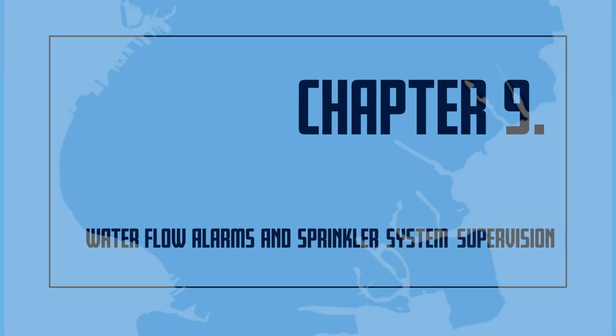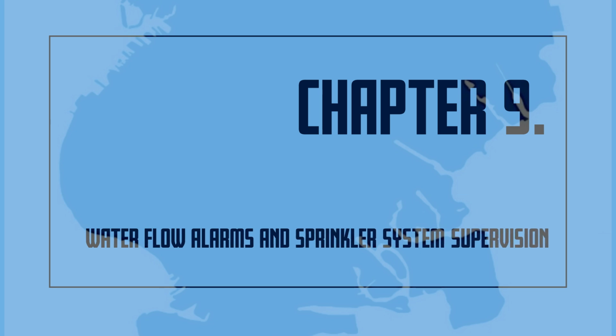9. Water flow alarms and sprinkler system supervision. Sprinkler systems should have devices and equipment for signaling when water flows through risers or mains supplying the systems. The flow may be due to fire, leakage, or accidental rupture of the piping. It is important that prompt action is taken when water flow is signaled by these devices.